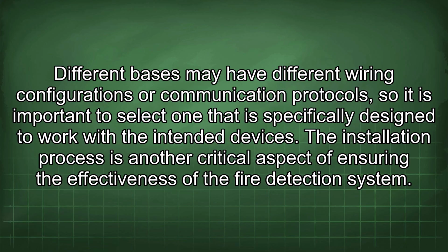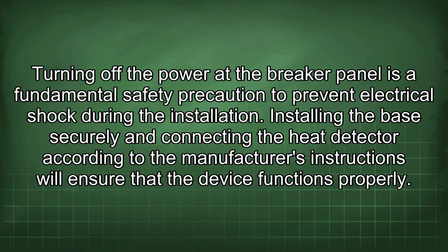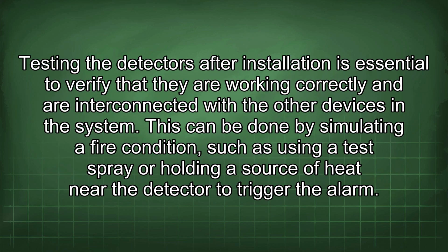The installation process is another critical aspect of ensuring the effectiveness of the fire detection system. Turning off the power at the breaker panel is a fundamental safety precaution to prevent electrical shock during the installation. Installing the base securely and connecting the heat detector according to the manufacturer's instructions will ensure that the device functions properly. Testing the detectors after installation is essential to verify that they are working correctly and are interconnected with the other devices in the system. This can be done by simulating a fire condition, such as using a test spray or holding a source of heat near the detector to trigger the alarm.